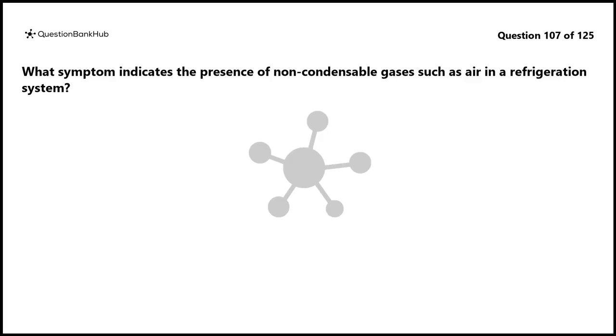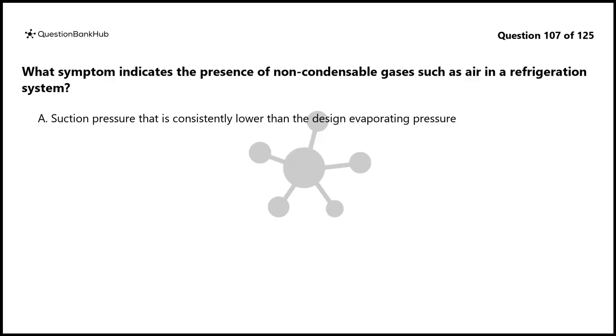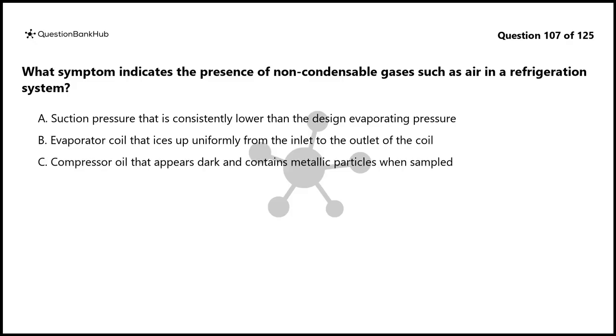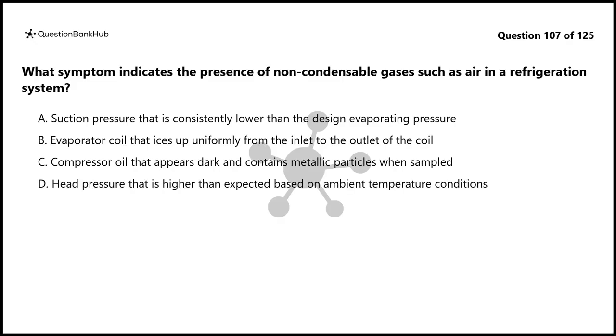Question 107. What symptom indicates the presence of non-condensable gases such as air in a refrigeration system? A. Suction pressure that is consistently lower than the design evaporating pressure. B. Evaporator coil that ices up uniformly from the inlet to the outlet of the coil. C. Compressor oil that appears dark and contains metallic particles when sampled. D. Head pressure that is higher than expected based on ambient temperature conditions.